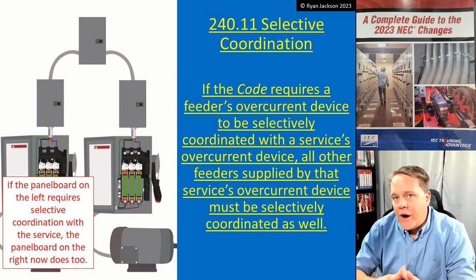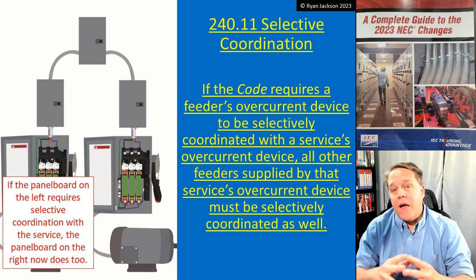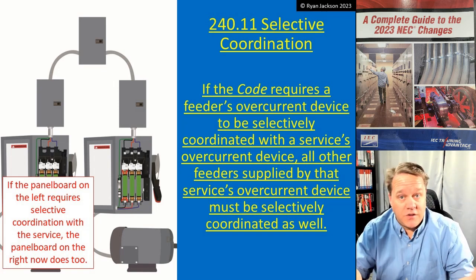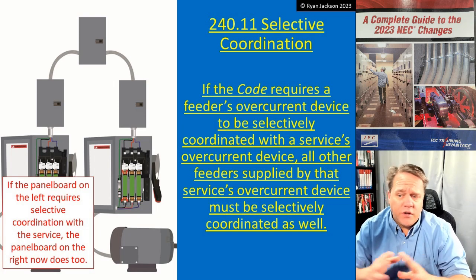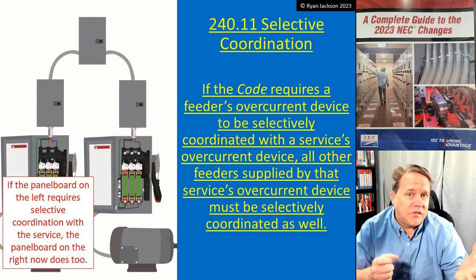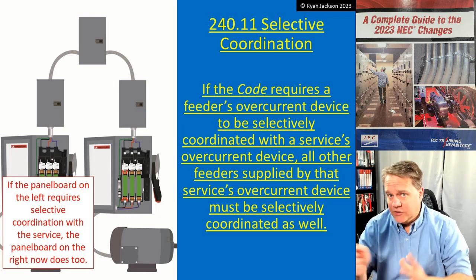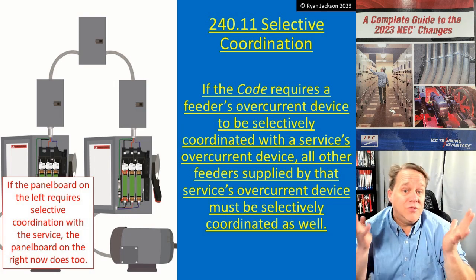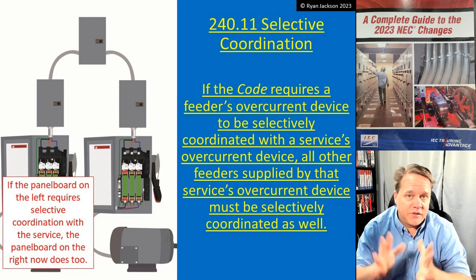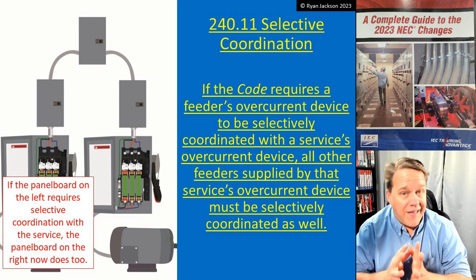We don't require selective coordination that often in the NEC. It might be something we strive for in the design of a building, but it might not always be possible - if you need to use a series-rated system, you're not going to be able to selectively coordinate the system; the two are opposites of each other. But there are some times in the NEC where we have to.